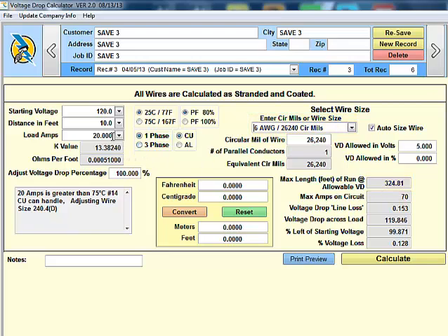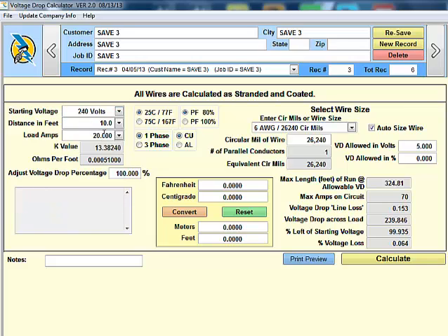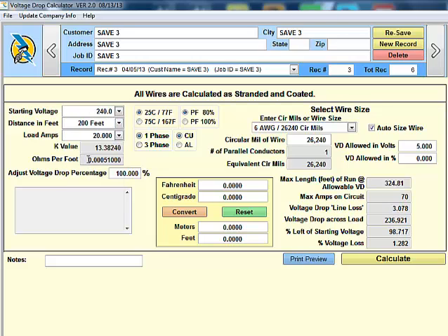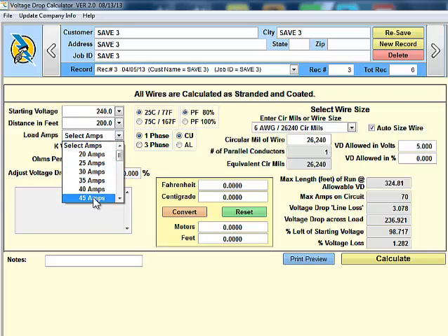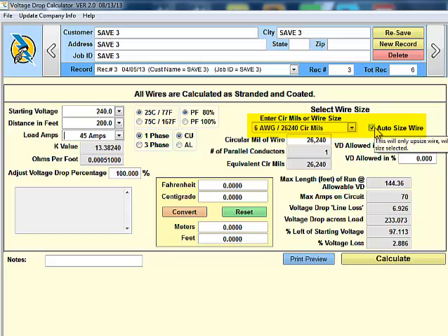Let's do another one here. Let's go ahead and use 240 volts as our starting voltage. We want to go 200 feet and maintain 45 amps. Notice what happened is, we've automatically selected 6 American wire gauge.